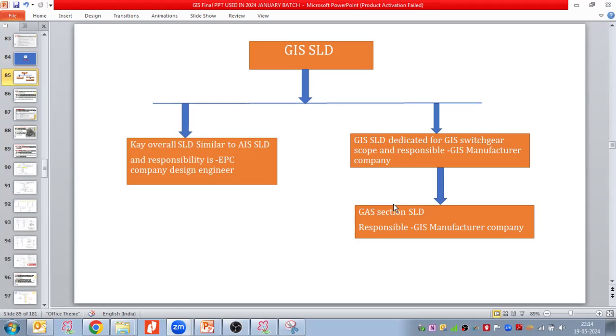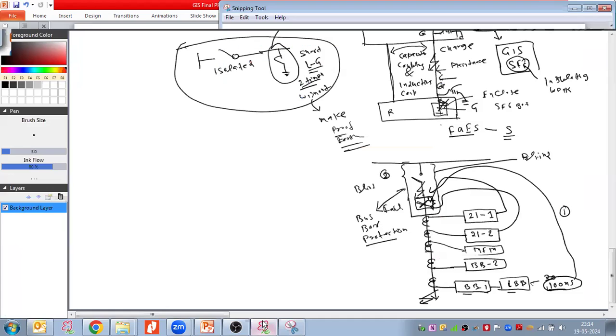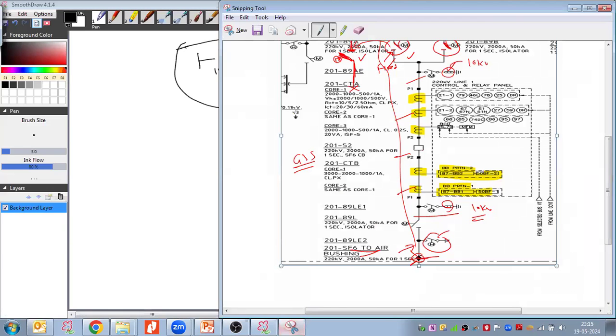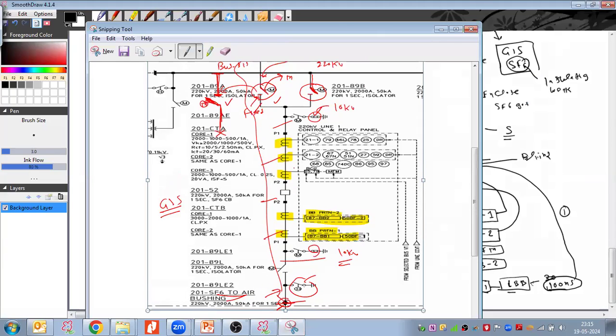Hello, sir. In the GIS, if you see the bus section and bus riser, in some cases we are using a circuit breaker, and in some cases only a disconnector in place of the circuit breaker. So is there any standard procedure? Are you telling me you are not using a breaker in the bay? No, sir, because we have a double bus bar. Okay, in that case we are using the bus coupler and bus riser as well.